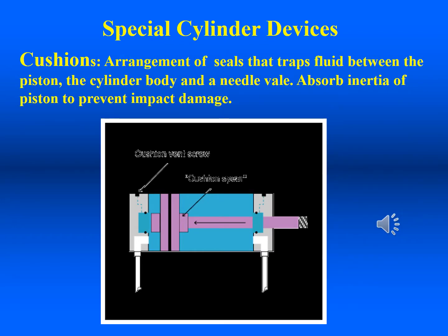Cushions are devices that trap fluid between the piston and the body caps to decelerate the piston and prevent impact damage, as well as inertia forces that may affect machine operation. In many cases, the cushions can be adjusted to obtain the desired amount of cushion, or they may be adjusted to eliminate cushion altogether. Cushions are found in both hydraulic and pneumatic cylinders. They are more necessary in compressed air systems because the actuators tend to move faster than they do in hydraulic systems.